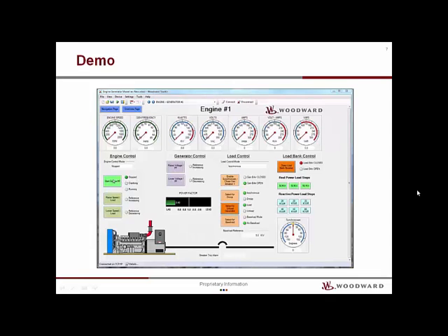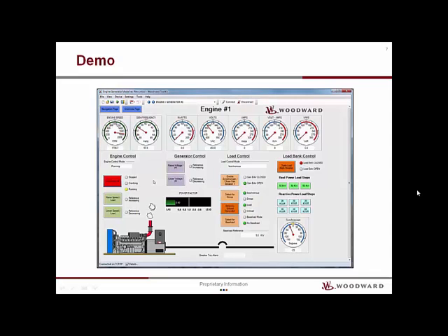Here is a demonstration of an isolated generator connected to a real and reactive power load bank. This screen is showing all of the information concerning speed, frequency, watts, volts, amps, volt amps, and VARs. The engine is started and comes up to 1800 RPM and 60 Hz on the generator. The load bank breaker is already closed, so I will close the generator breaker.